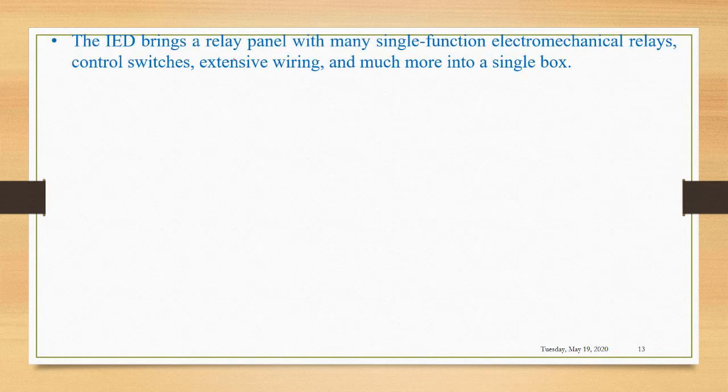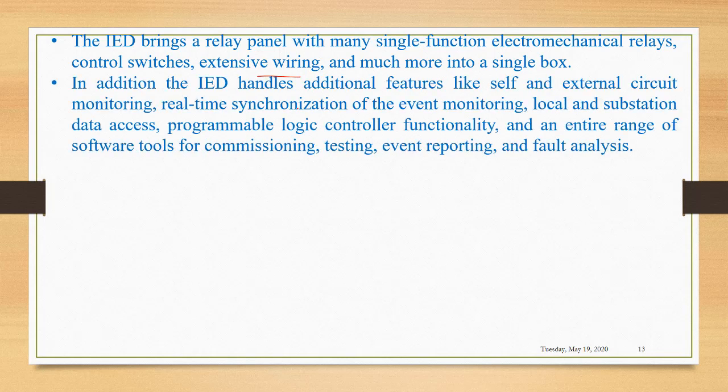The IED brings a relay panel with many single function electromechanical relays, control switches, extensive wiring, and much more into a single box. In addition, the IED handles additional features like self and external circuit monitoring, real-time synchronization of the event monitoring, local and substation data access, programmable logic controller functionalities, and an entire range of software tools for commissioning, testing, event reporting, and fault analysis.